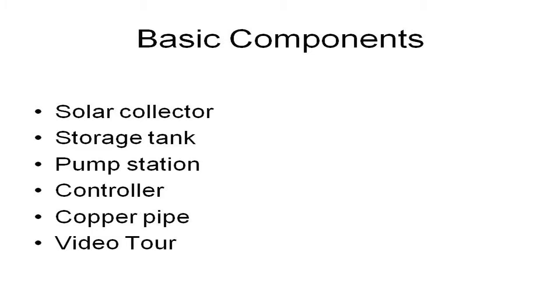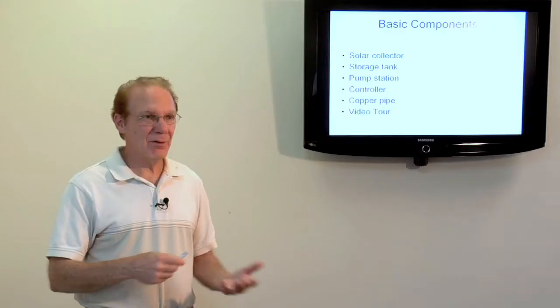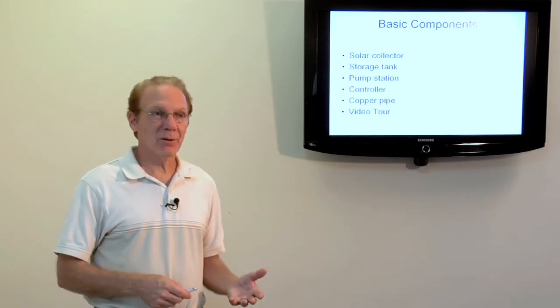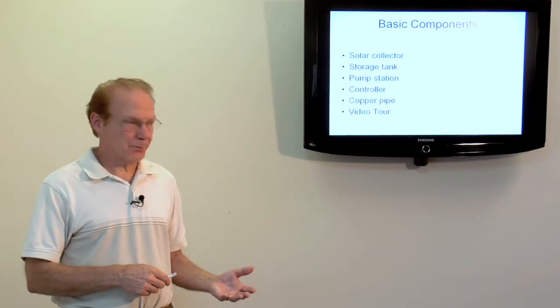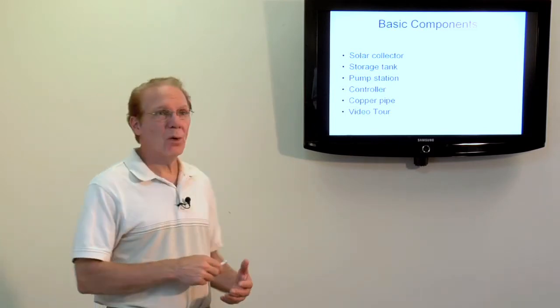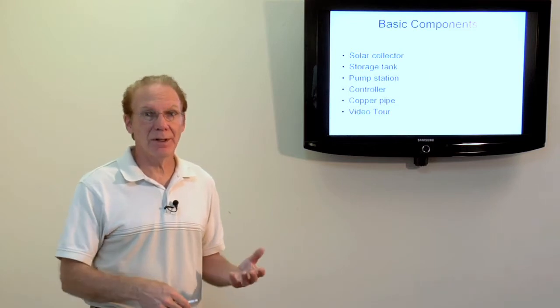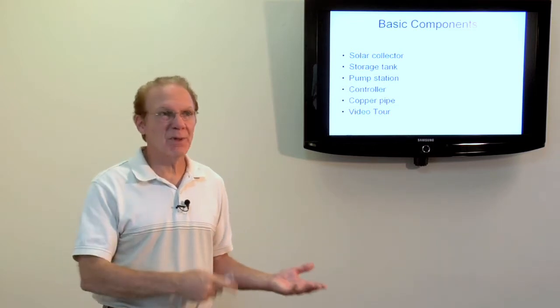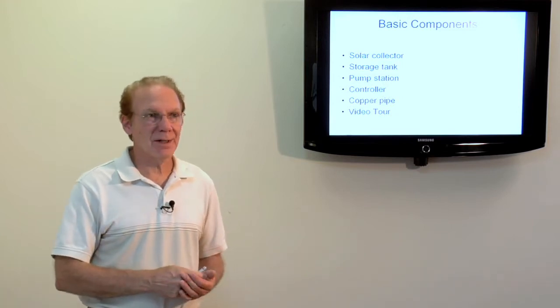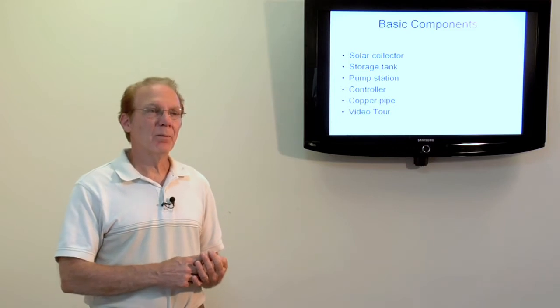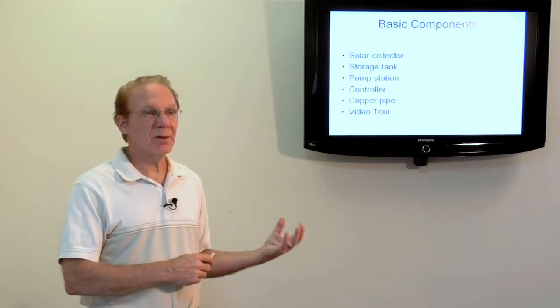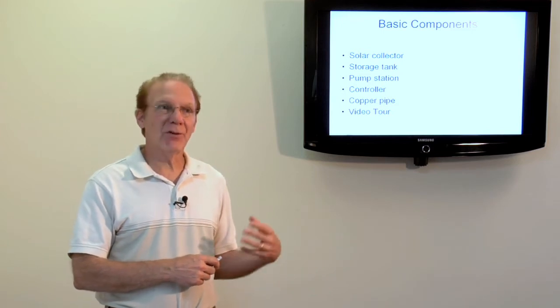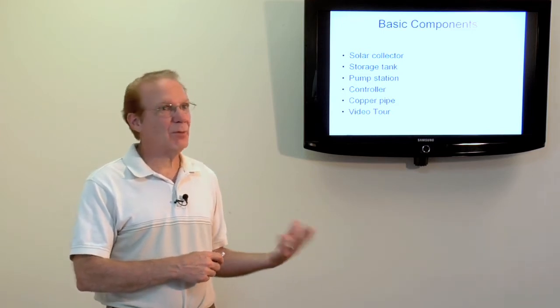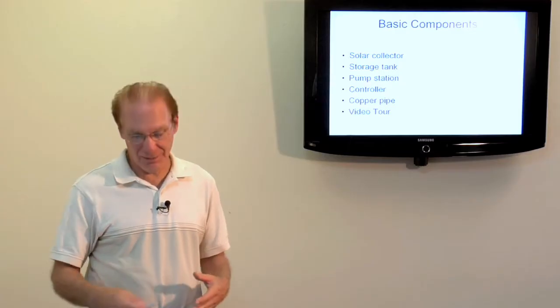Copper pipe. There's a lot of different pipe around today, PVC and PEX and all this, but the temperatures on a solar hot water system can exceed 160 degrees. So we generally use copper pipe on the loop between the collectors and the hot water tank. Inside the house, you're still fine to use PVC or PEX or whatever you've already got. It's not going to cause any problems because we have a device for safety purposes that limits the water temperature going to the house. It also extends the tank temperature because if we have 140 degrees stored in a tank and we're only delivering 125 degrees to the house, then that hot water lasts longer.